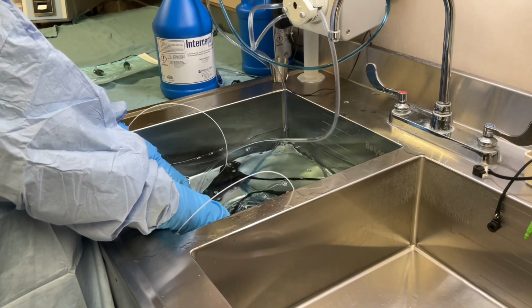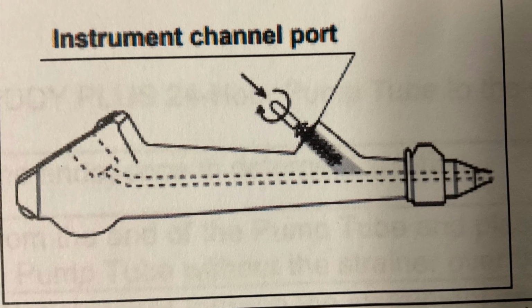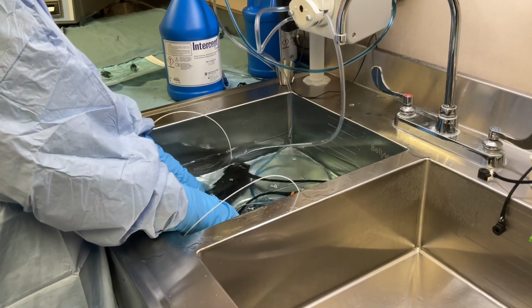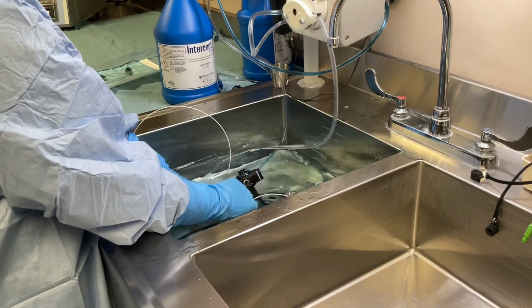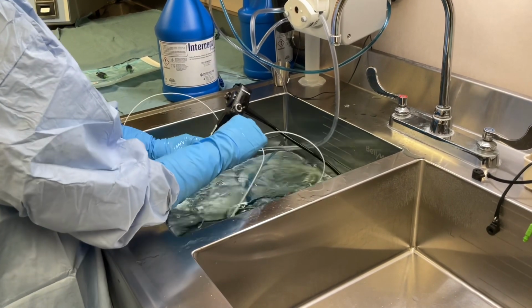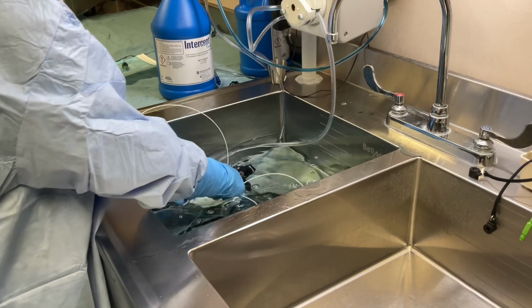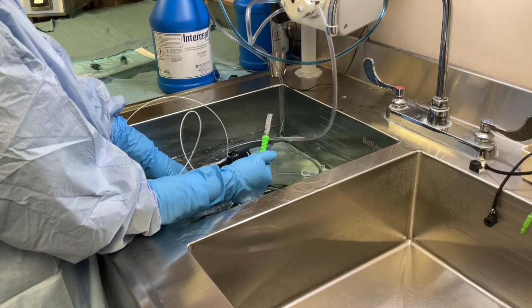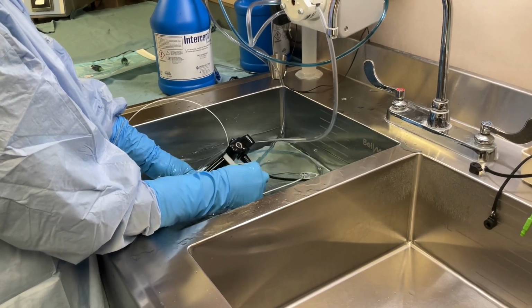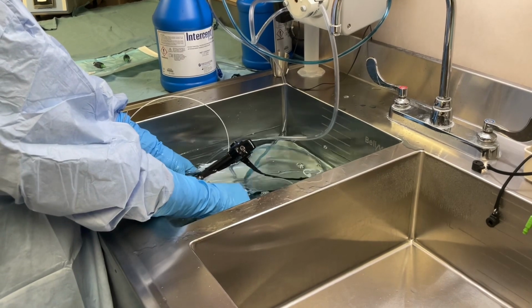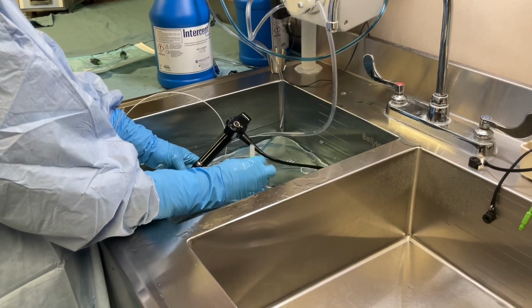Brushing instrument channel port. Use the fat end of the brush to clean the instrument biopsy port. Insert the brush gently, turn it once, and pull it out of the opening. Clean the bristles and repeat until all debris is removed.